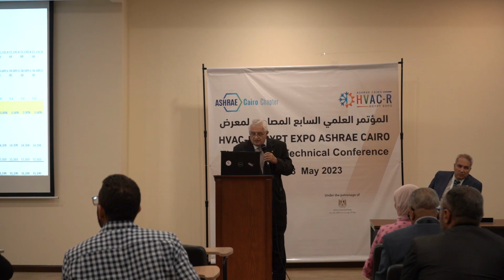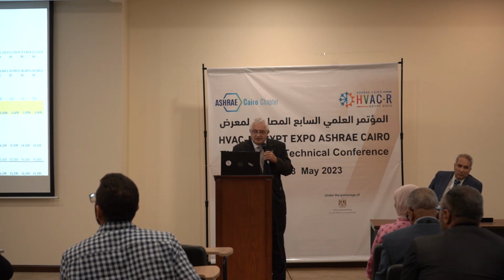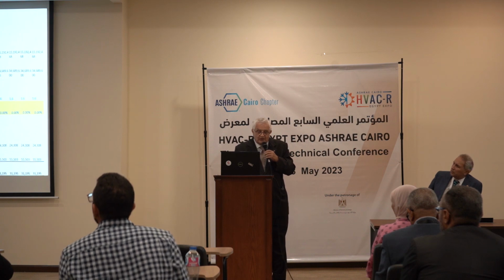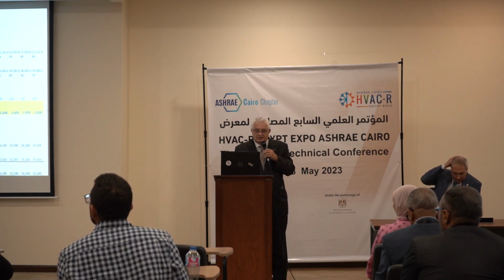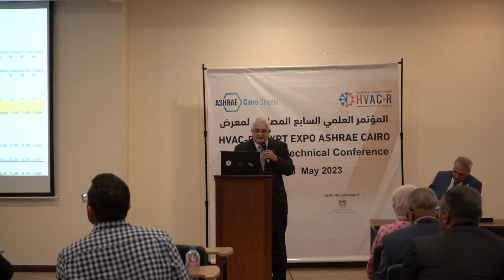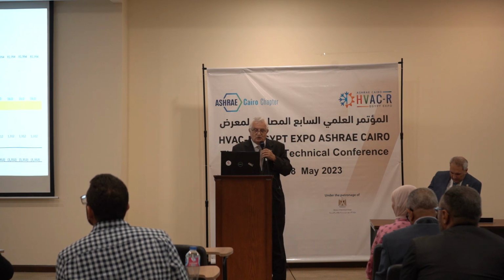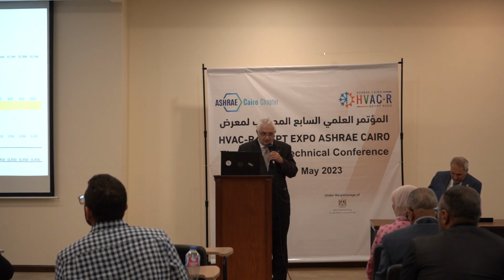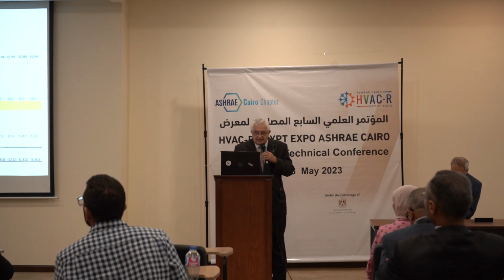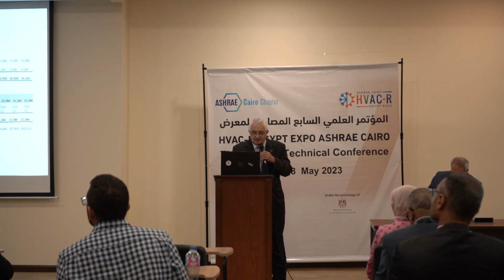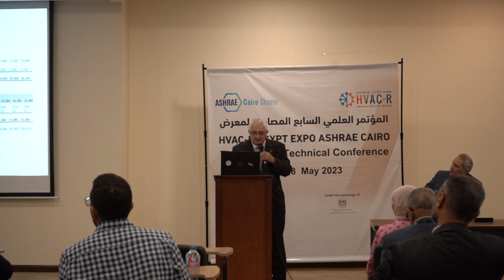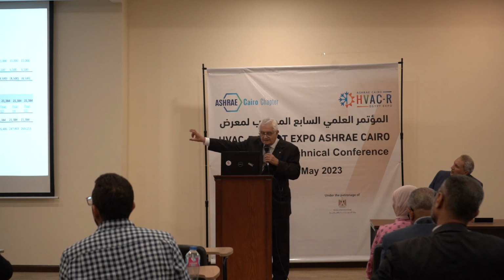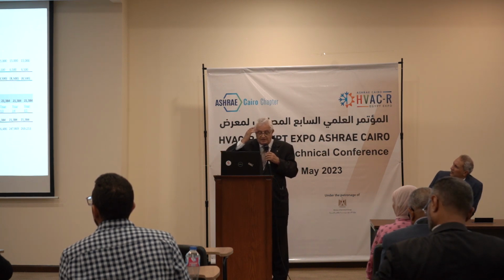And then the second part of the financial model is to calculate the power consumption of the IEC hybrid unit and the DX unit, and then calculate the electricity cost of both machines over 15 years. And then compute the water consumption. Of course, water consumption will be for the IEC machine only. And then we calculate the water cost, and we see this difference in cost over 15 years. And then we put them all together and see the net cash of the unit when you add to it the maintenance. And we arrive at this rectangle at the very bottom of this page.